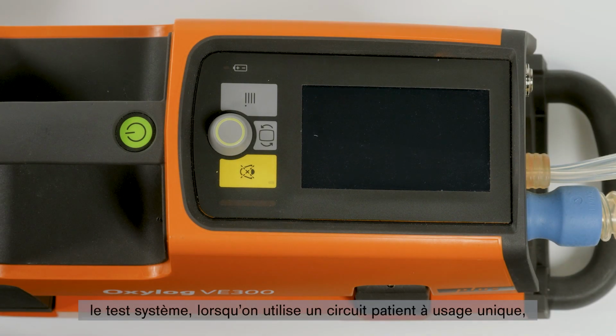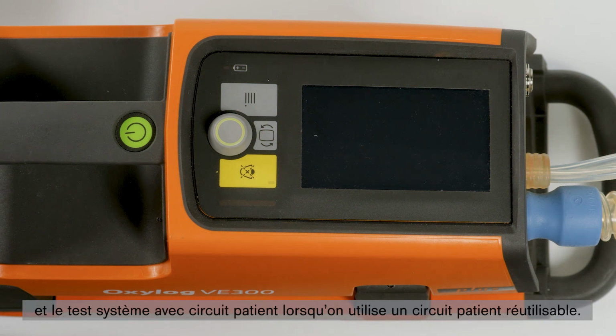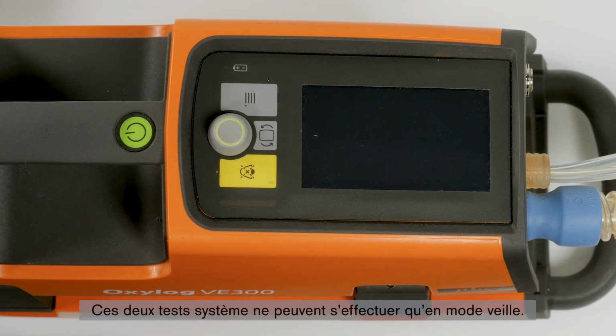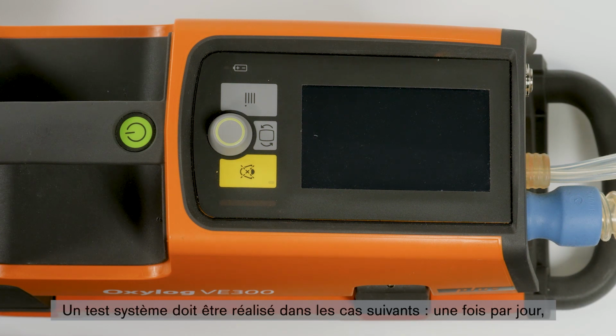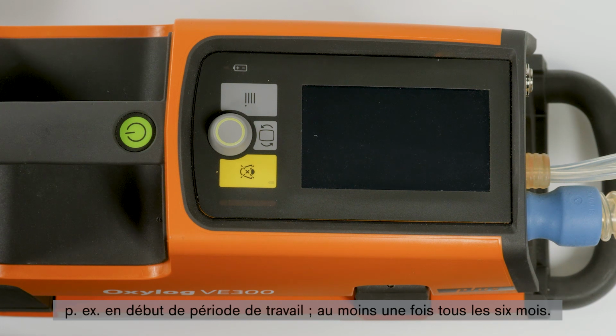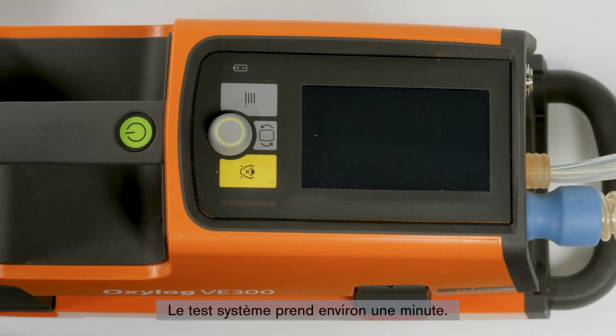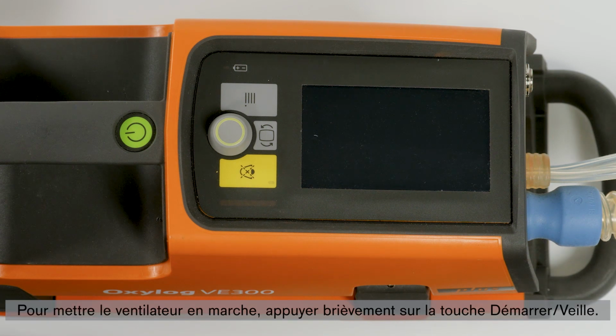The device has two different system tests. The system test when using a disposable breathing circuit and the system test with breathing circuit when using a reusable breathing circuit. Both system tests can only be performed in standby mode. A system test must be performed once a day, for example at the start of a shift, but at least every 6 months. The system test takes about 1 minute.